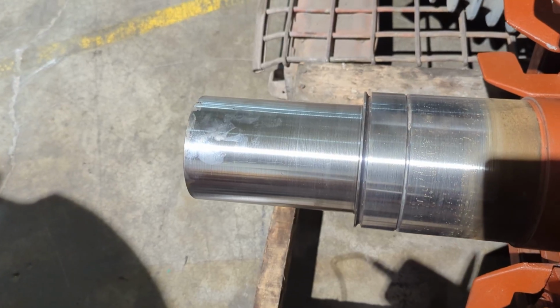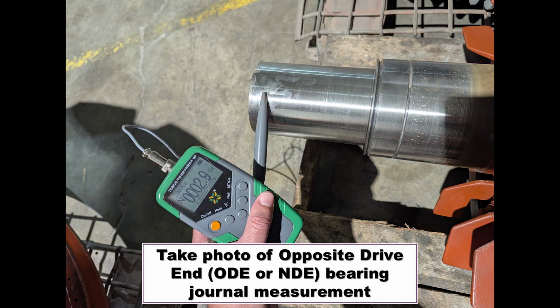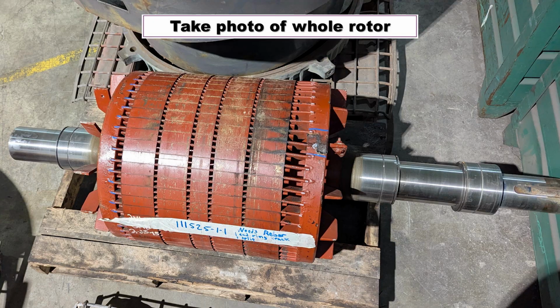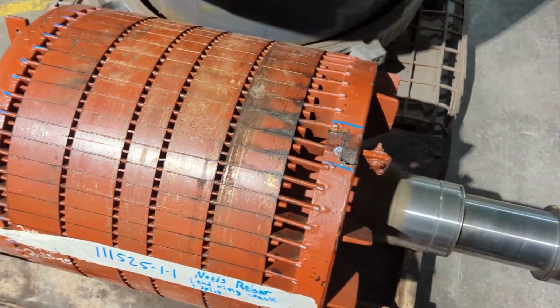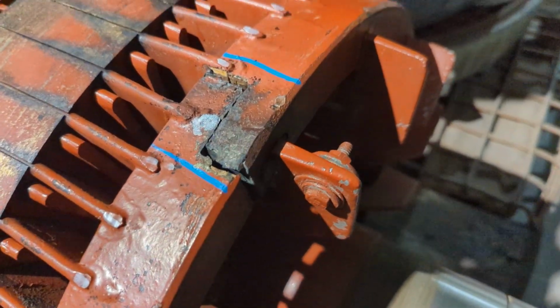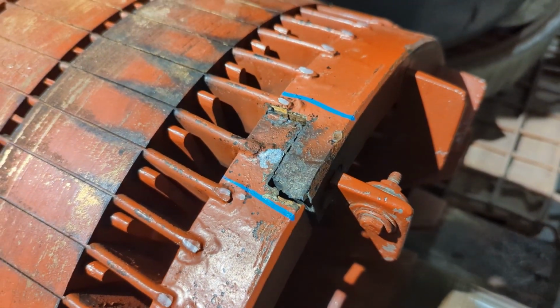I want to take some photographs of the measurements. And then of the rotor itself. Now this specific one, I can clearly see that we've had a failure of the end ring.